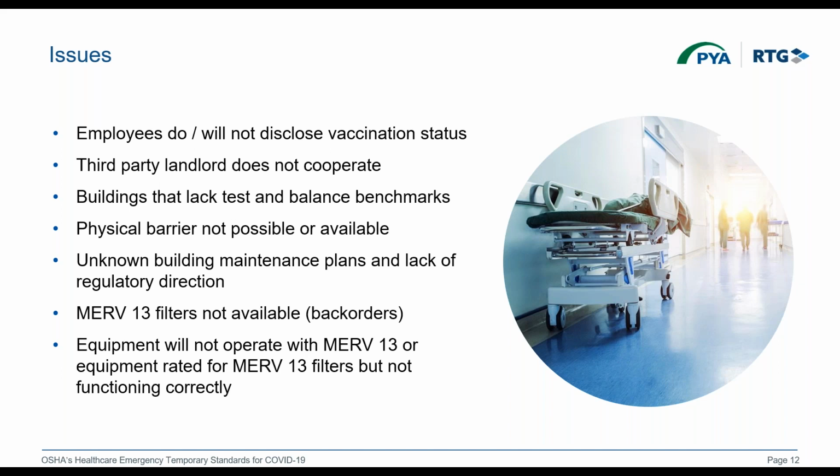MERV 13 filters not available. I don't want to say very few, but a lot of organizations were not utilizing these standards of filters up until 3 weeks ago, and then they tried to buy them, and they're not available, and it'll be months before they are. So what's really happening now is people are asking, well, can I get MERV 11s? And that's really not a great solution, because it starts to step you into a more restrictive airflow for your system that's probably old. And so you're going to have some challenges with just buying and finding the equipment you need.